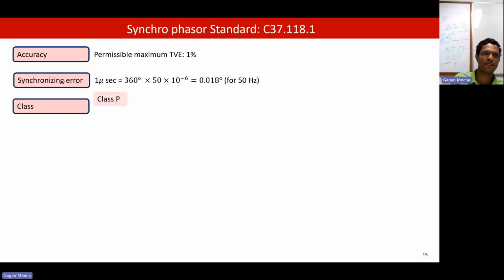These are the standards for accuracy that has to be maintained for the PMU. The maximum permissible total vector error is 1% TVE, which is the difference between the estimate minus actual, squared and summed, divided by the actual squared sum. This should be less than or equal to 1%. And there is synchronizing error, because we have measurements between two PMUs.